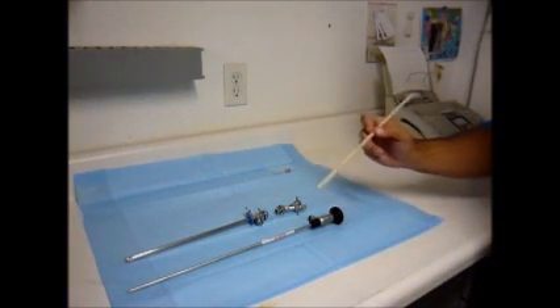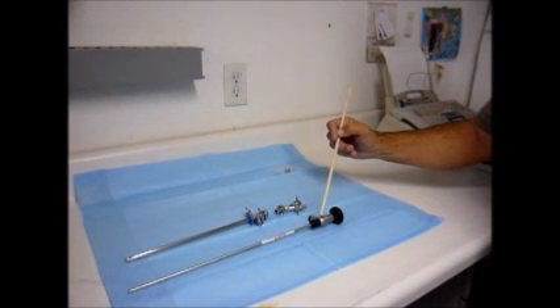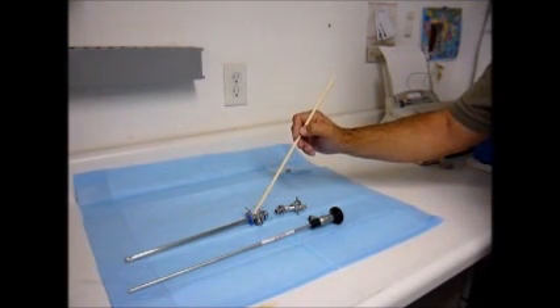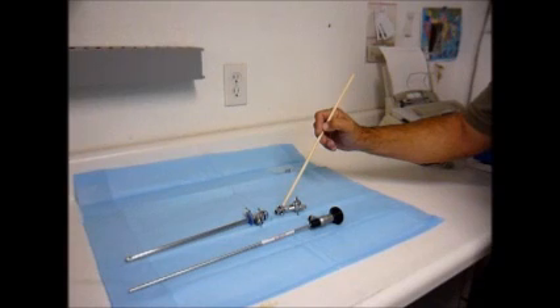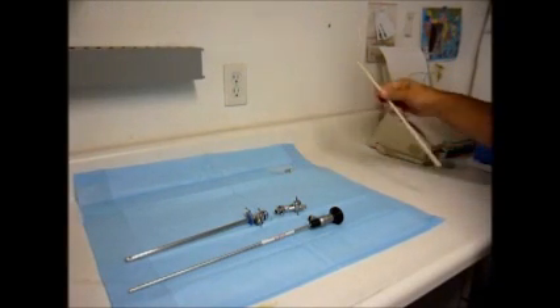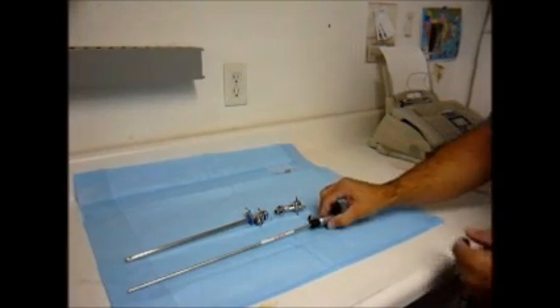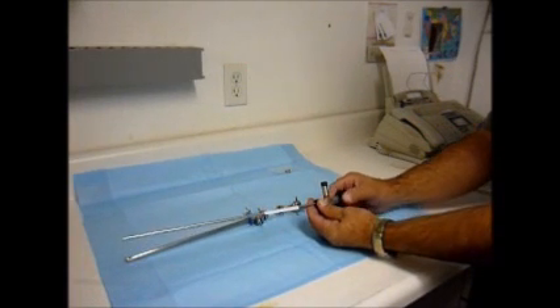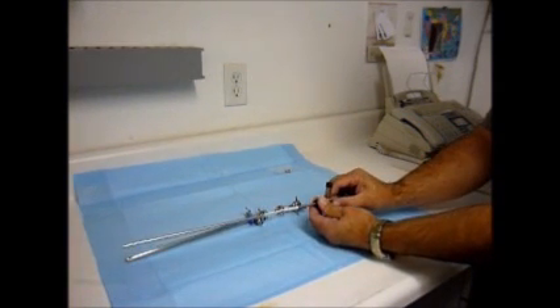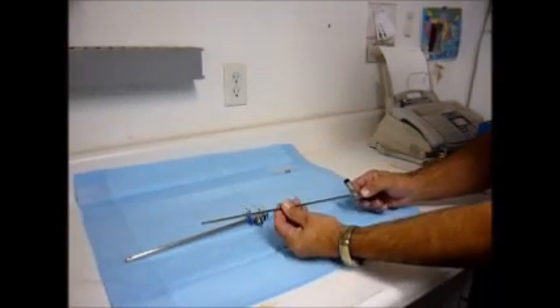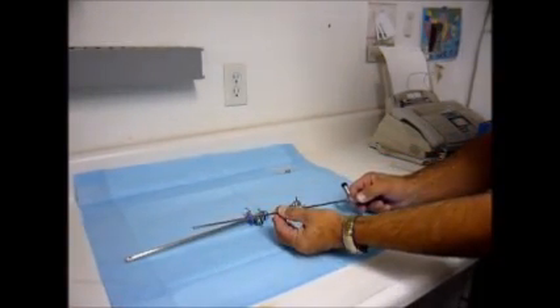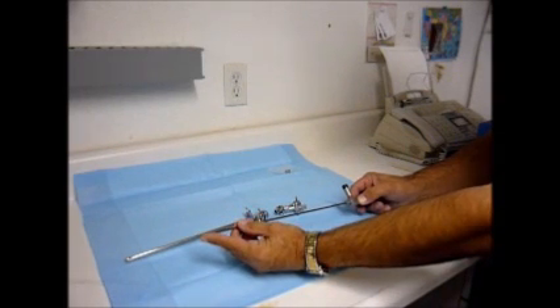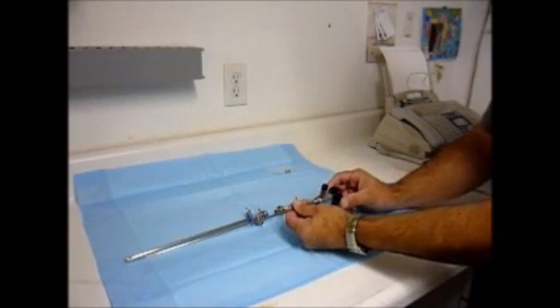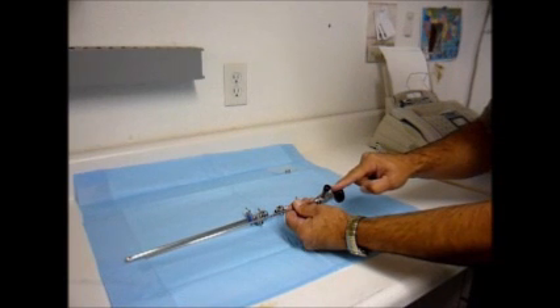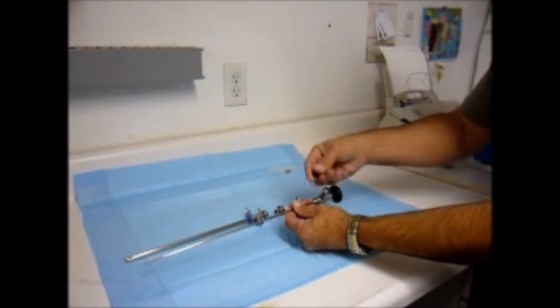The next series of instructions is how to connect the rigid endoscope to the operating sheath and single horn bridge. This is done by first removing the protective sheath on the rigid endoscope. By making a 1/4 turn and pulling off the stainless steel protective tube, you now expose the endoscope shaft and distal lens. Also attached to the scope is a protective cap.